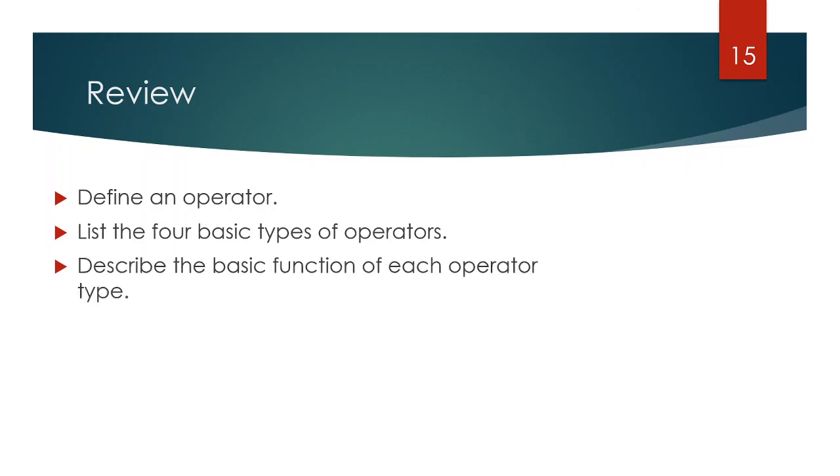The function of each: a momentary push button can be used to momentarily cause an action, and when that button is no longer depressed, it will no longer take that action, where a latching push button will take that action and repeat that action until it is unlatched. A selector switch will either maintain a particular selection or momentarily make a particular selection based on the rotation of the actual selector switch itself.